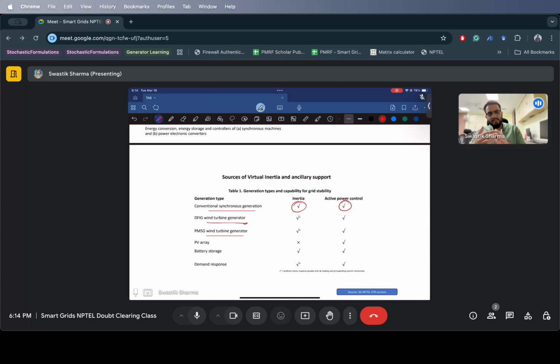Synchronous generators are able to provide inertial response because they are connected directly across the grid and sense the grid's frequency. But in wind turbine generators, both DFIG and PMSG, permanent magnet synchronous generator or double fed induction generator, even though both have rotating mass, rotor, and turbines, because their rotor is connected through a power electronics based converter to the grid, it is not directly connected across it. So it is not able to provide inertia by means of that rotating mass.